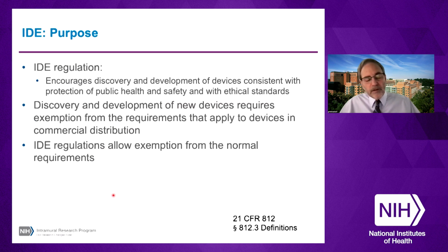So when Congress enacted the medical device amendments, they recognized that in order to develop and discover new devices, those new devices had to be exempted from the requirements that normally apply to devices in commercial distribution. Remember, I said devices had to be legally marketed to be used in humans. But if you're studying a new device that's not legally marketed, well, you have to have a get out of jail free card on that. So what the investigational device exemption regulations do is they exempt the new device from all of these requirements.